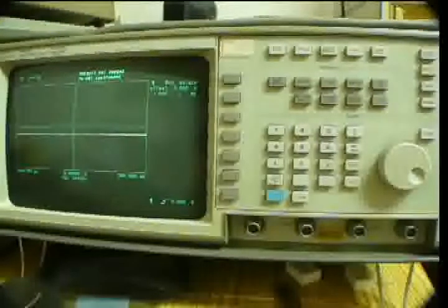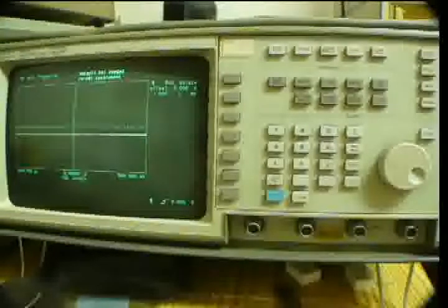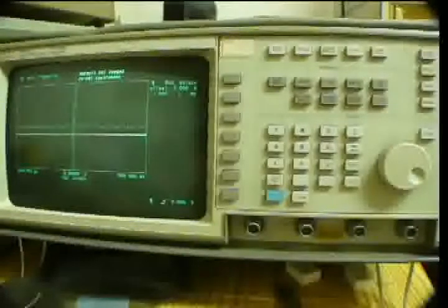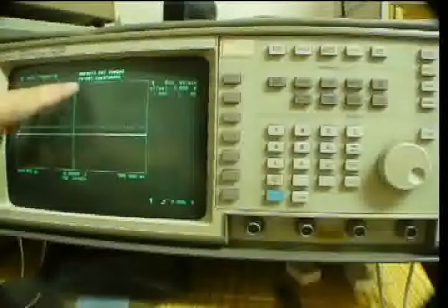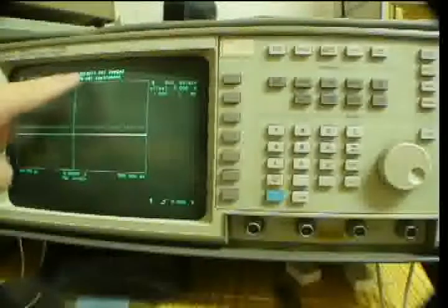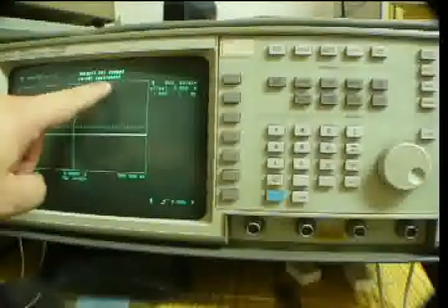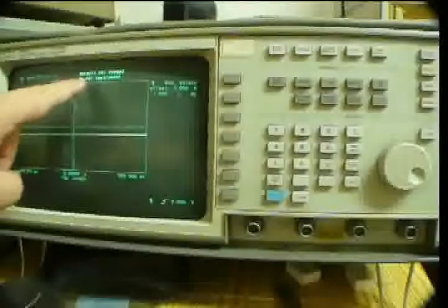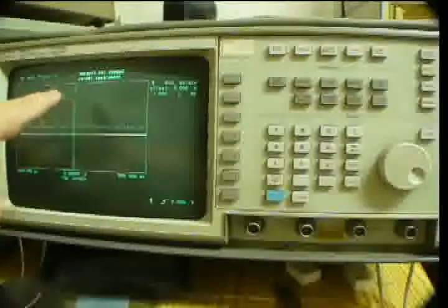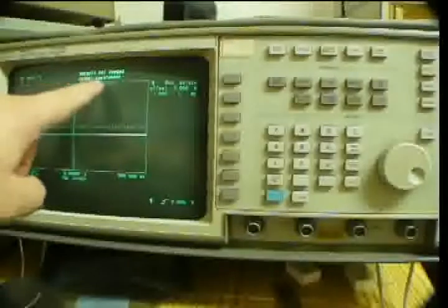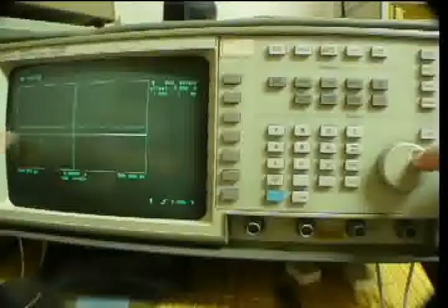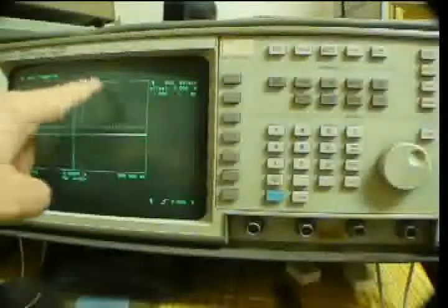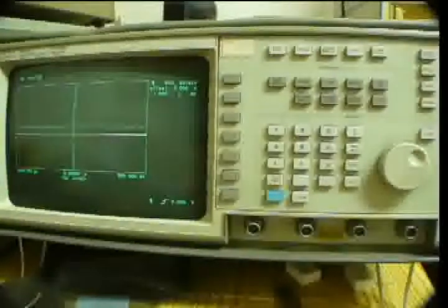Because I reset it, it doesn't have any previous calibration in there. So the screen shows that it needs a default card loaded and to recall instrument. I don't have the proper equipment to do that, so I just push the button and let the prompt disappear.